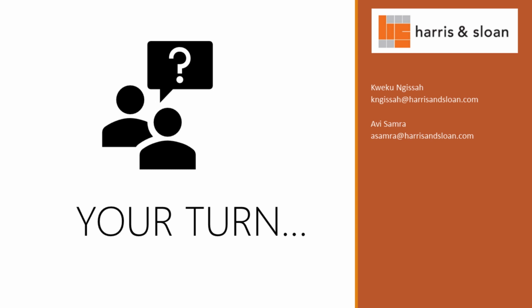The question is what this is based on—minimum code requirements, what method, optional? Yes, however, under 220.82 it assumes you have nameplates for every item in the home, which is never the case when designing. Hence the standard method is recommended.